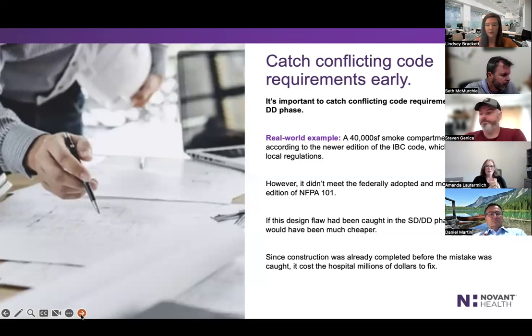So we'll talk about smoke compartments. In the International Building Code, the requirement for a smoke compartment is 40,000 square feet, and Novant Health hired an architect who followed that International Building Code requirement. You might know that NFPA 101 does not require 40,000 square feet — their smoke compartment requirement is about 22.5, but don't quote me on that. Yeah, you're correct, perfect. So that's a much more stringent requirement for fire safety than the International Building Code.